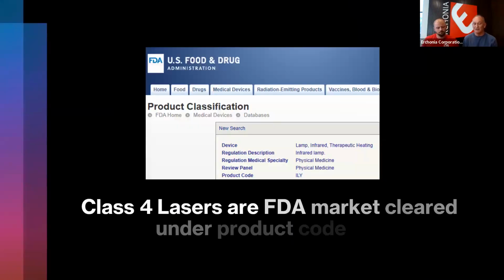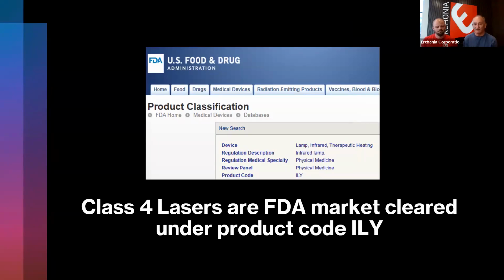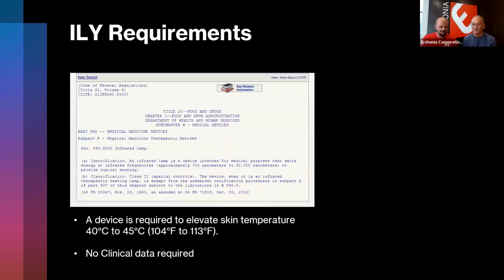When you start looking at infrared lasers or topical heating devices, this is the category they're under: infrared lamps for therapeutic heating. This is different from low-level lasers, which are in a completely different category called NHN. The ones for topical heating are ILY. And I'll let Steve take a lot of the FDA, even though I deal with them now.